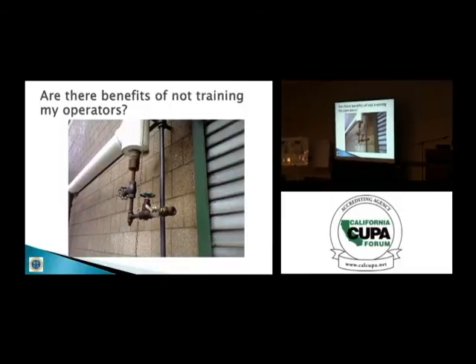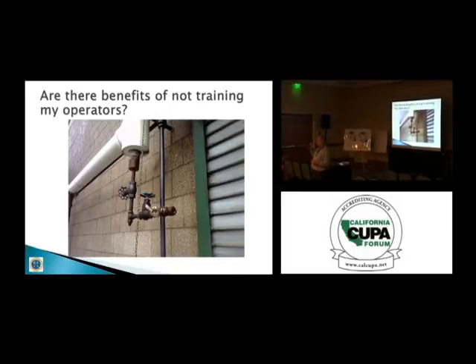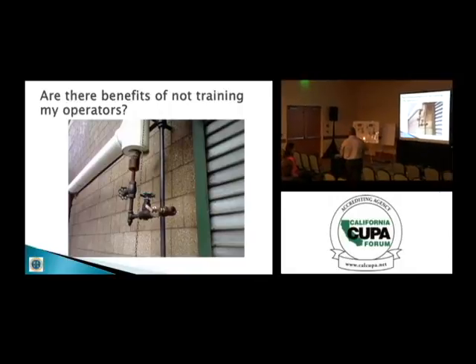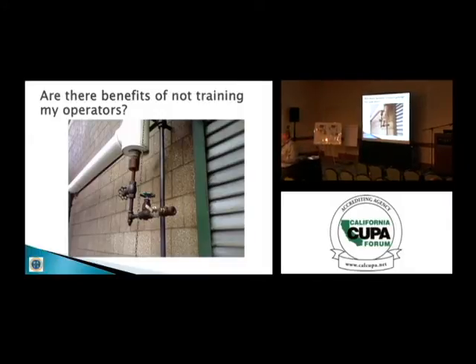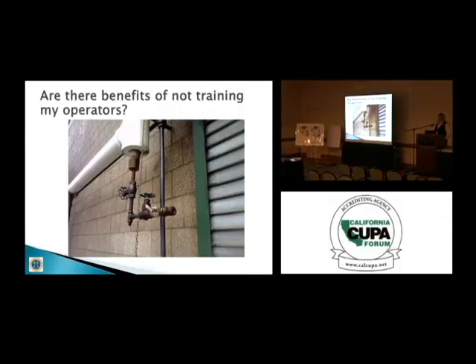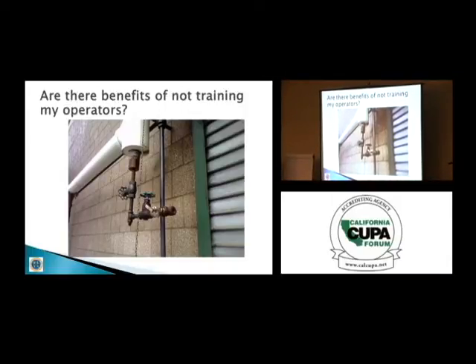There are some systems that provide vessels to collect the oil, so that you can limit the amount that can come out of the system if something goes wrong. Others don't have that; this is part of the live circulating system. Having the dead man valve as the permissive is a great tool. You've got the primary valve where your operator is throttling the rate of the oil removal, and the dead man is the permissive. If it suddenly is no longer dispensing oil, just a spit of liquid, all he's got to do is, oh my God, and it's terminated. He can close the valve, open the other valve, and his task is done.